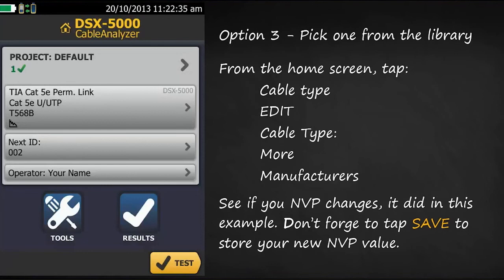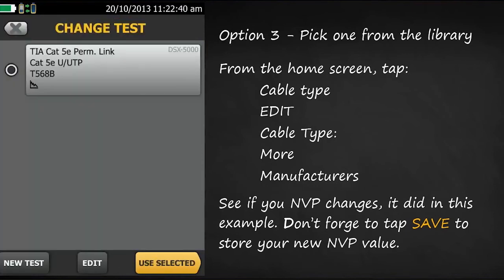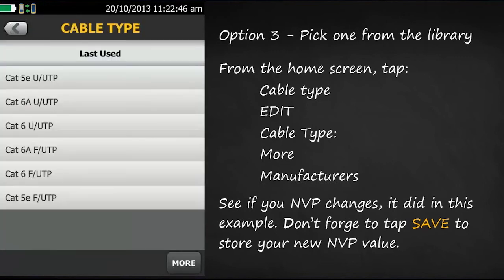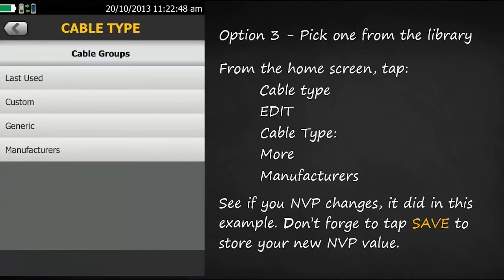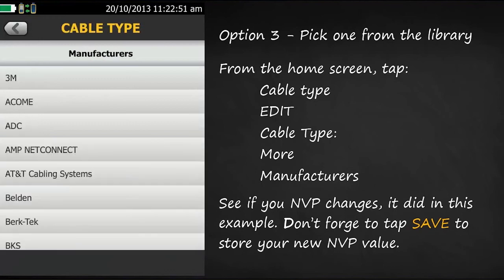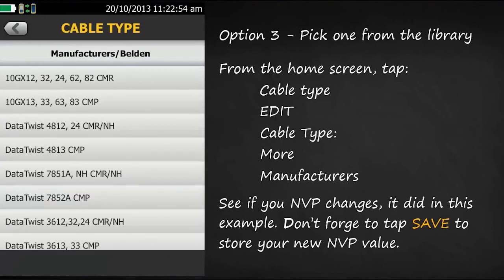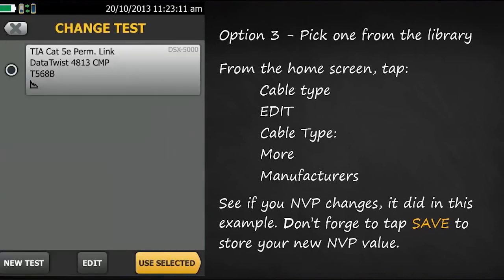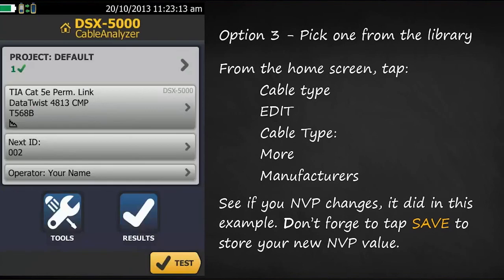The final method is to choose one from the cable library. From the home screen, tap your cable type, then edit. Where you see cable type, tap more, and you'll see manufacturers at the bottom. Select a manufacturer — for example, Belden — and you'll see the NVP value changes, in this case to 70%. When you change the cable type in the library, it looks up the database in the tester and presents you with the stored value. Tap save, use selected, and you'd be ready to begin testing.